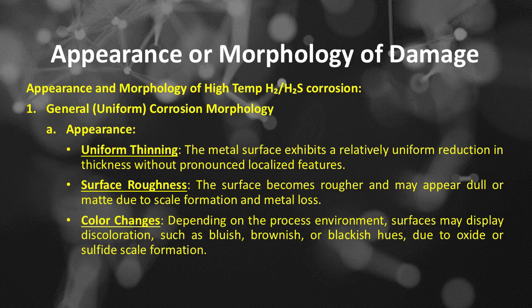The metal surface exhibits a relatively uniform reduction in thickness without pronounced localized features. Surface roughness. The surface becomes rougher and may appear dull or matte due to scale formation and metal loss. Color changes. Depending on the process environment, surfaces may display discoloration, such as bluish, brownish, or blackish hues, due to oxide or sulfide scale formation.